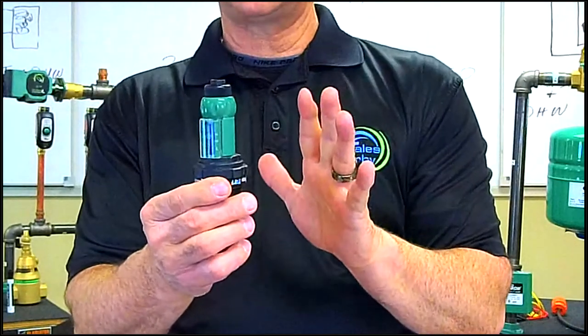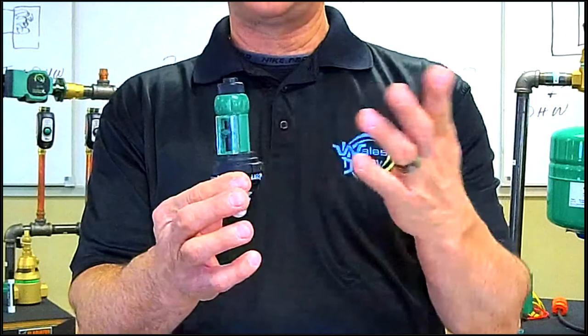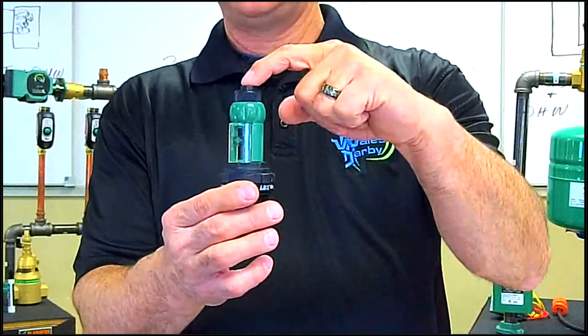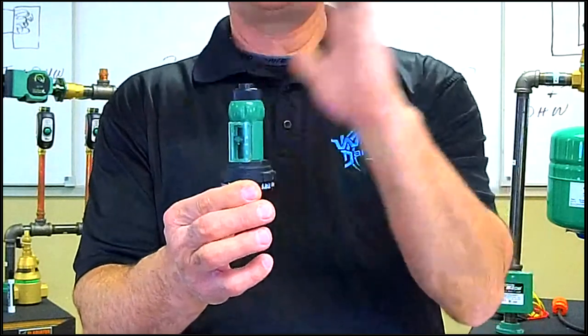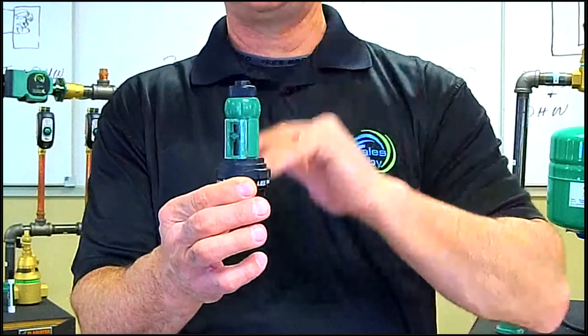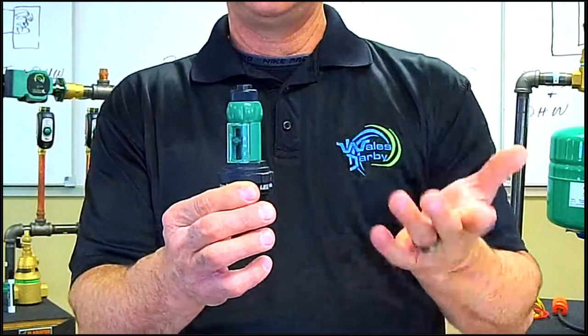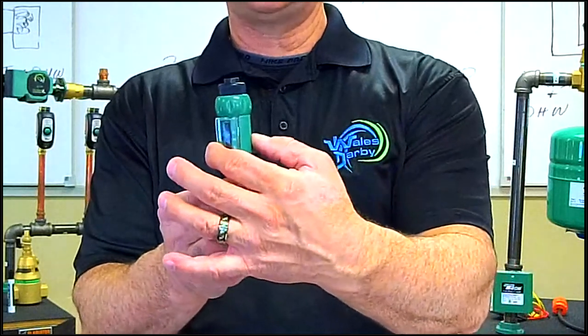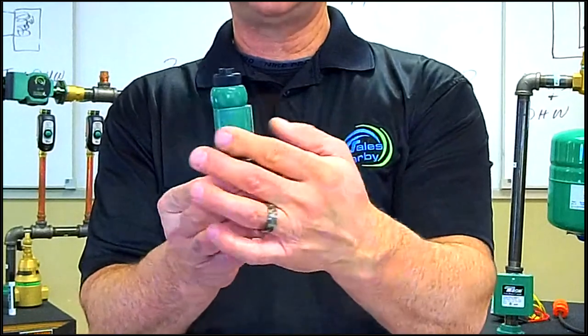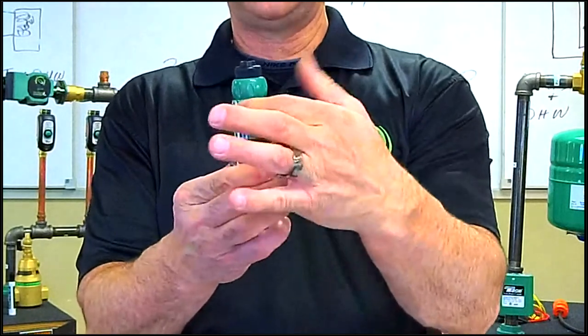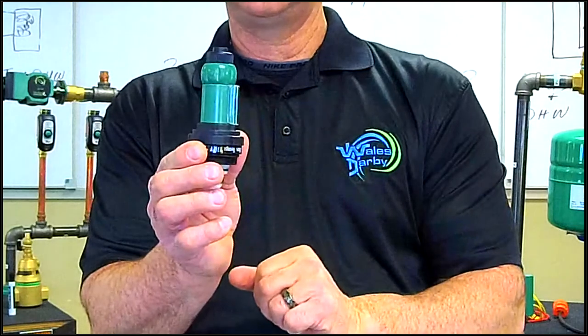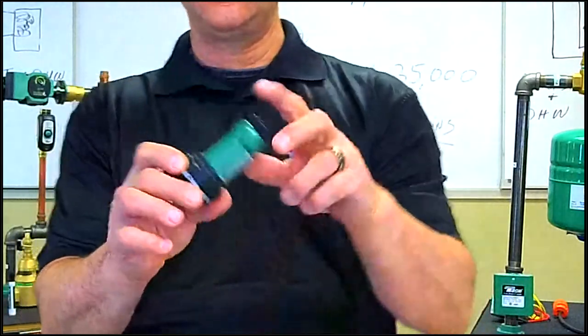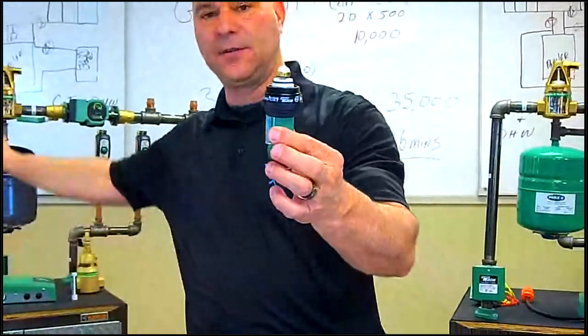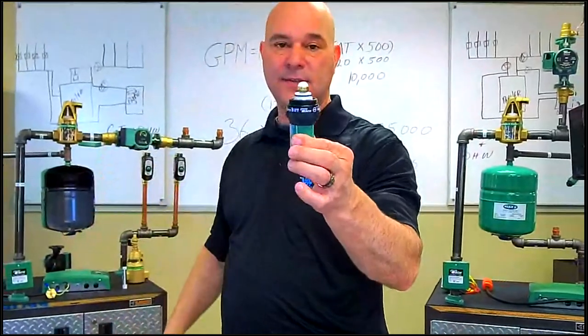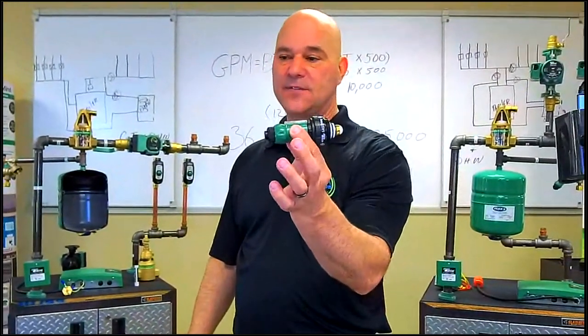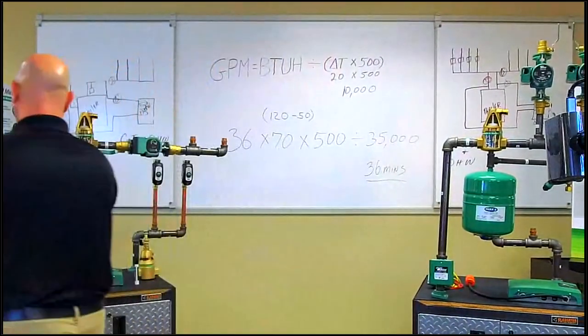And the nice thing about this, you don't have to worry about it blowing off the relief valve. If I set this to 26 PSI, I just push this button one time, the feeder will fill to 26 PSI and shut off. If this is in an area where you can't see it, this is nice because I can rotate that sight glass anywhere I need to so that I'm in a position where I can see it. This is replaceable on the unit. You don't have to take the body out. This is replaceable. That's the feed valve side of that feeder backflow.